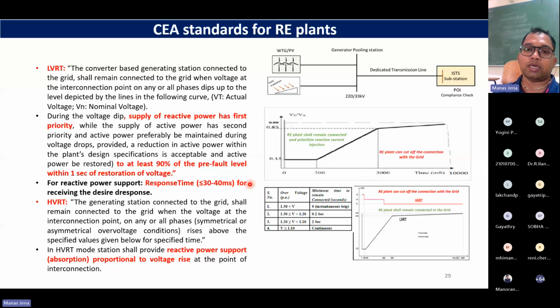X axis, this is y axis. This is Vt upon Vn. Vt is actual voltage upon nominal voltage. Let us say this is 0.85, this is 0.15. If you are in this region, let us say the voltage is 0.7. So the voltage becoming 0.7 should not mean that you will isolate yourself. No, no, no. If it is 0.7, you can see till this much time you can remain connected. This time is in milliseconds. So that is what we are referring to as LVRT.